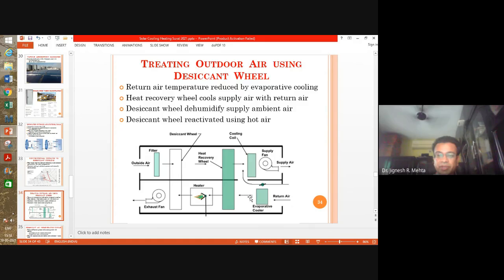So here what you are doing is you have low enthalpy air here. You are further reducing the temperature. You are cooling this stream of outside air with the help of a heat recovery wheel, and with the help of this desiccant wheel, you are removing the moisture from it, and that moisture is taken away by the hot air and then exhausted into the atmosphere, right? So where will this heat come from? Here it's shown as if you are burning something, a fossil fuel, but it can come from a solar thermal collector also.